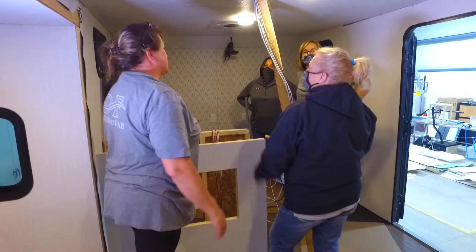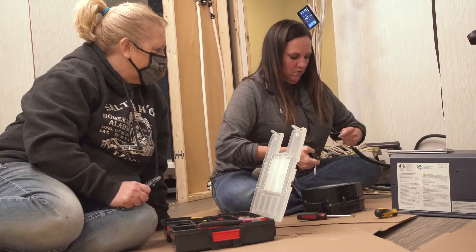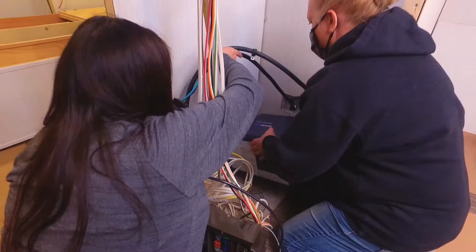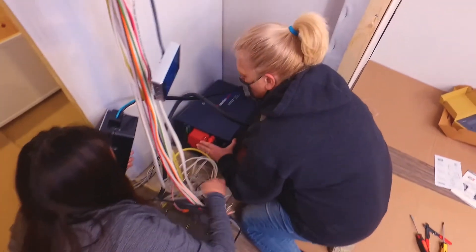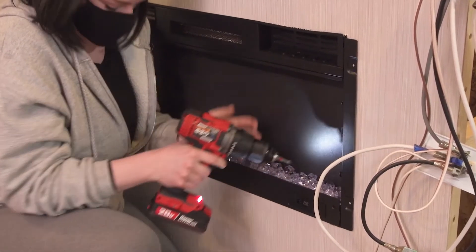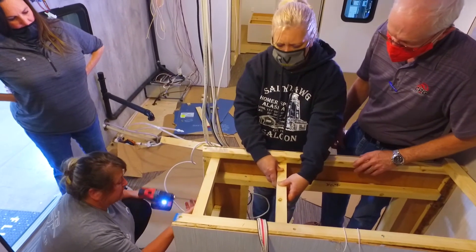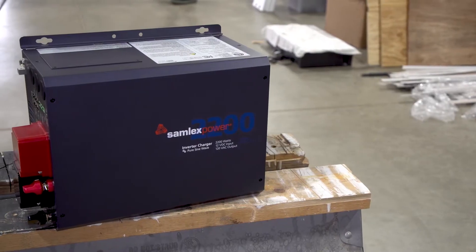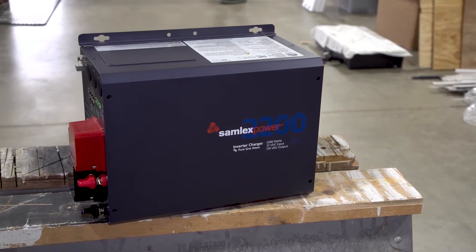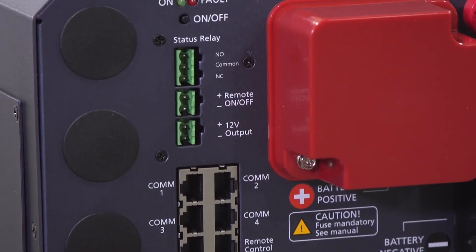My job today is to install the Samlex EVO-2212, which is a three-in-one inverter — it has an inverter, a battery charger, and a transfer switch all built in. Drive to Fab is all sponsorship driven, so all products have been donated by sponsors. We reached out to Samlex America because they're a great company to work with. It's a three-in-one device combining a 2200-watt DC-to-AC power inverter, a 100-amp battery charger, and a 30-amp transfer switch.